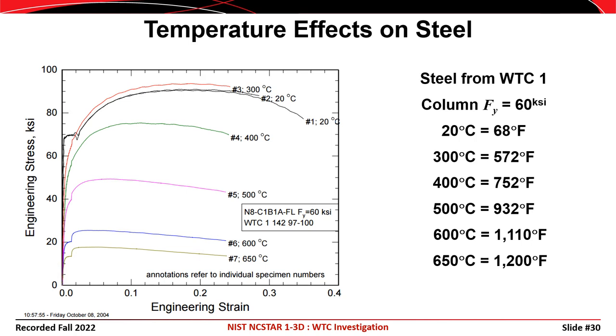If the temperature is increased a bit further, you can start to see significant losses in strength and stiffness at 400 degrees Celsius and beyond. The loss in strength has obvious effects on the performance of the structure, but the loss in stiffness can be as detrimental or even more so than the loss of strength, since the buckling strength is a function of the modulus of elasticity.